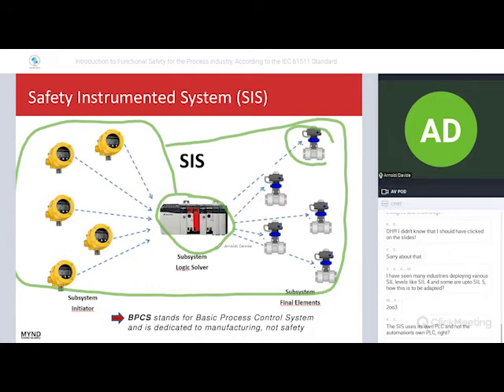One other term is the BPCS. BPCS terminology means basic process control system, and it is dedicated to the manufacturing, not to safety. It is addressed only to production. Inside the BPCS, you can find, for example, the distributed control system and the PAC for production, including all field devices, but it is addressed only to production, not to safety.